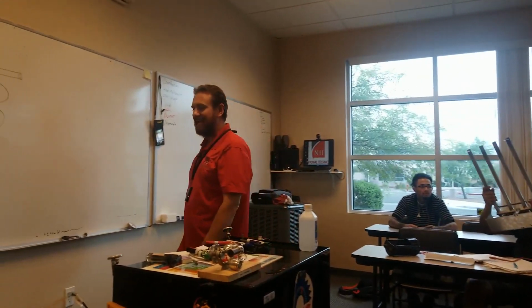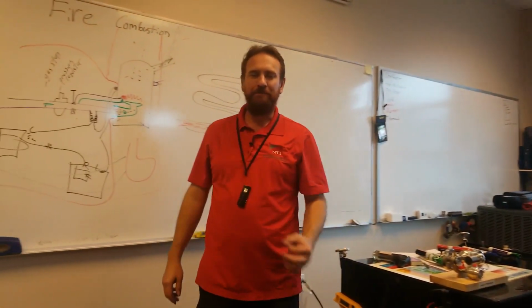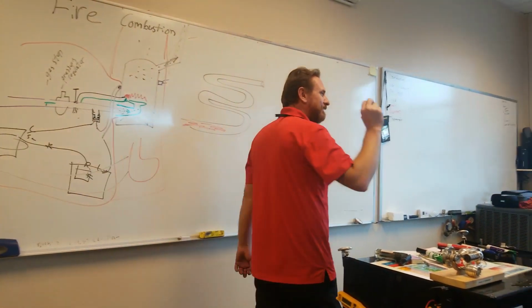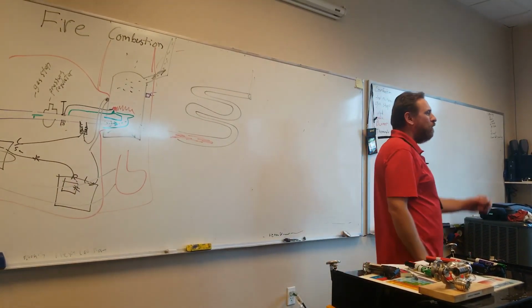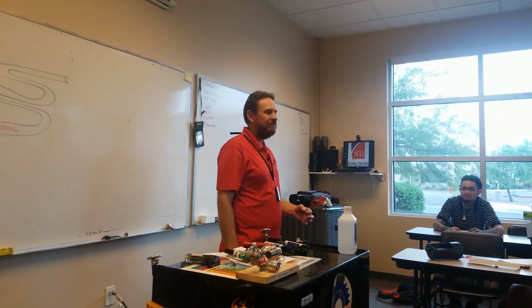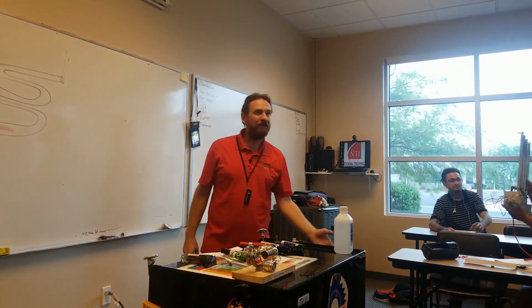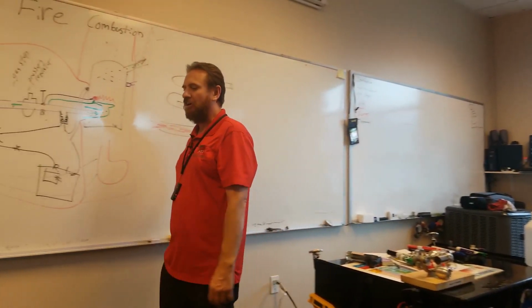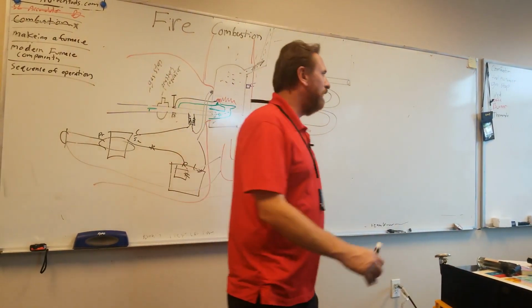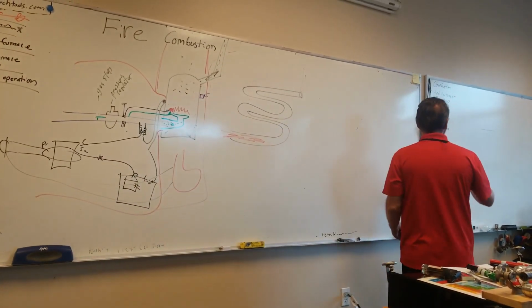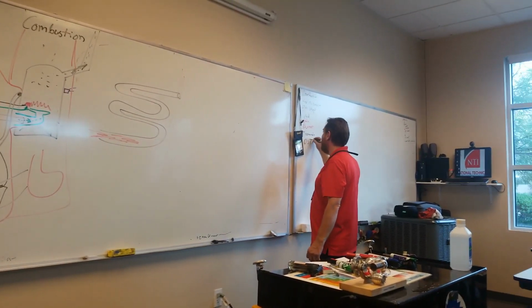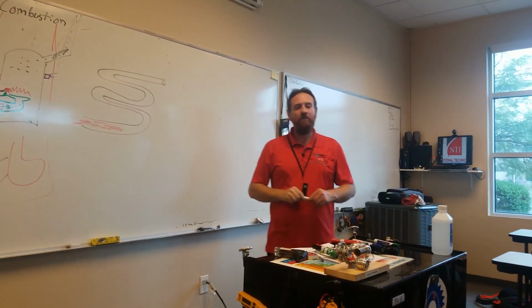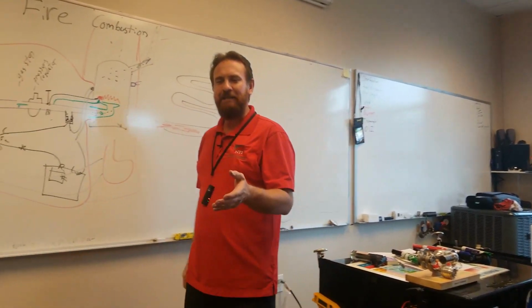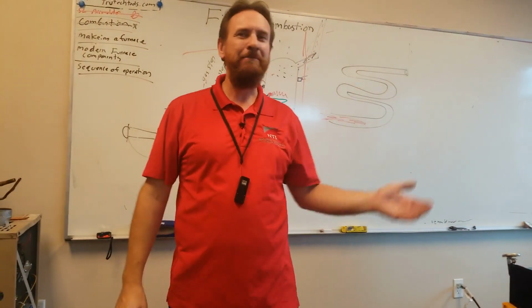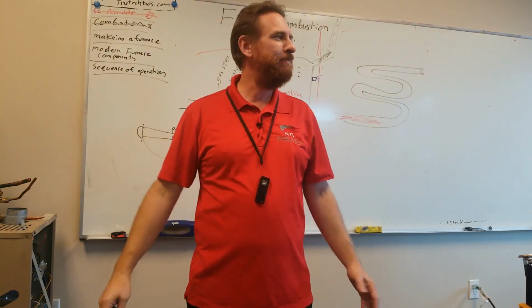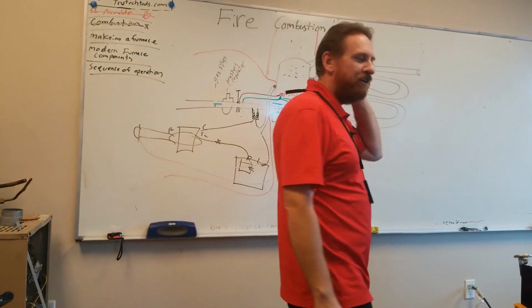But then they said, hey, instead of having a spark igniter light the pilot first, what if we used a spark igniter to light the main burner? They started calling that DSI. It's called direct spark ignition. Does that eliminate the pilot? Yes, eliminated the pilot immediately. We just said, instead of lighting the pilot light and then the pilot light lighting the main burners, how about we use a spark to light the main burners? So they started doing that.